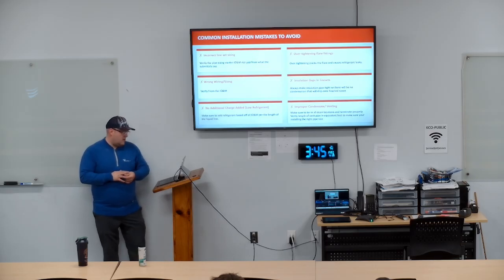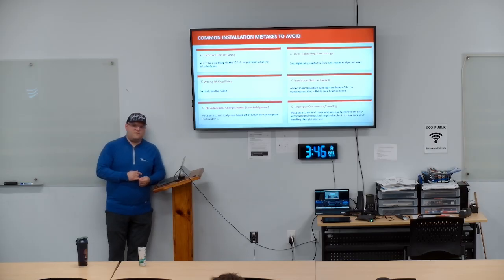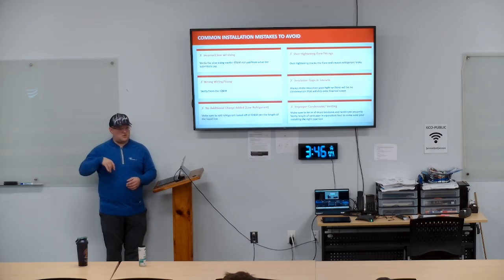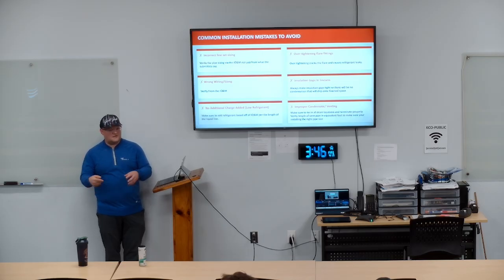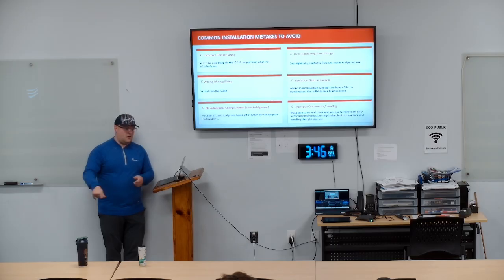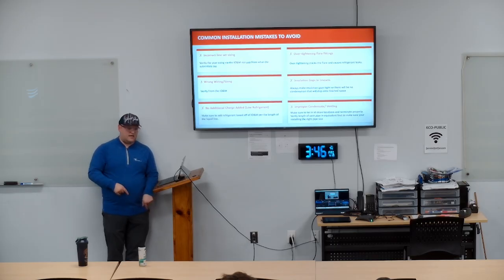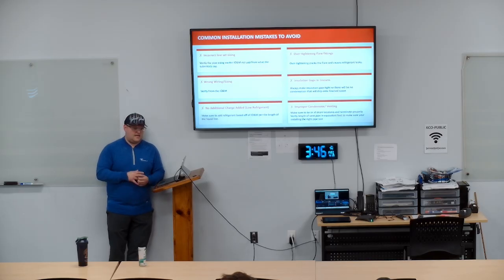No issues. I'll help. Condensate, high efficiency furnaces that are tied into a split, is what they'll call it, a little residential unit outside. High efficiency, all of them have a condensate off of the inducer motor. I go down, tie in. So you tie off the coil, condensate comes off, cool, we're good. We got it tied in. No, you don't. There's another point halfway down the furnace. You open, you put the adapters on, pop it out the side, heat it together and take it down. All right. Again, it's in the IOM book. So make sure you're reading that so we don't miss it.